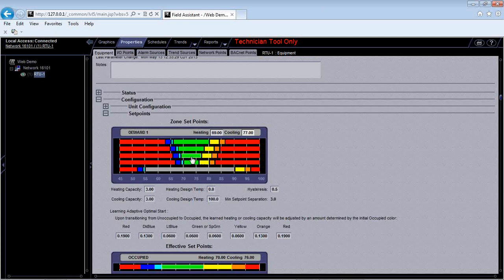So you have three different levels. I have demand level 1, where I have broader set points, demand level 2, and demand level 3. Now you need a separate program to do this demand limiting, to read the power coming in and to load shed with this controller. But the controller program is set up ready for it on the rooftop unit. You just need a separate program to say, hey, I'm on peak load 1, you go to demand limit 1. I'm on peak load 2, go to demand limit 2. So it's a great energy saver if you're actually doing the power metering, but that's something you have to do separate. Okay. Scrolling down, I wouldn't mess with all this stuff.